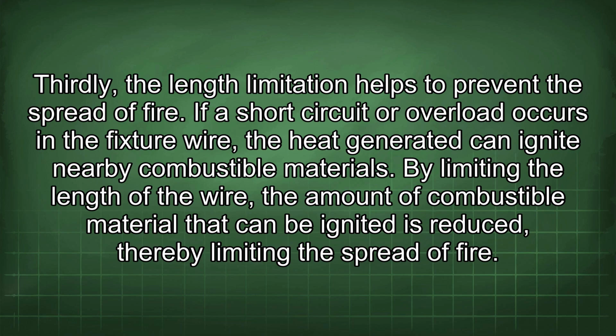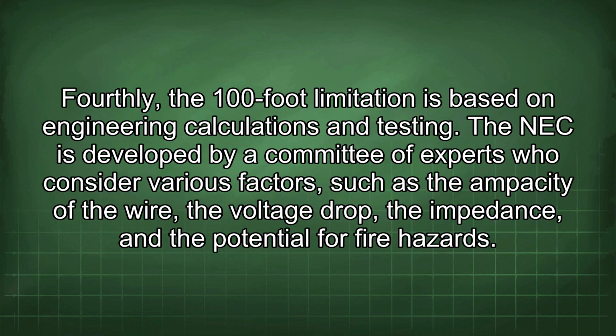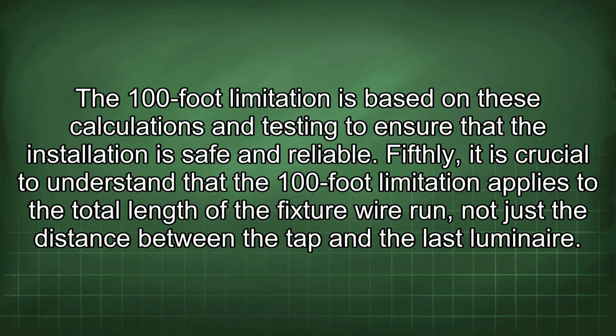Fourthly, the 100-foot limitation is based on engineering calculations and testing. The NEC is developed by a committee of experts who consider various factors, such as the ampacity of the wire, the voltage drop, the impedance, and the potential for fire hazards. The 100-foot limitation is based on these calculations and testing to ensure that the installation is safe and reliable.